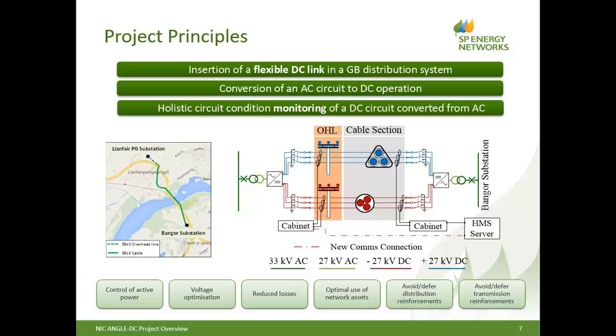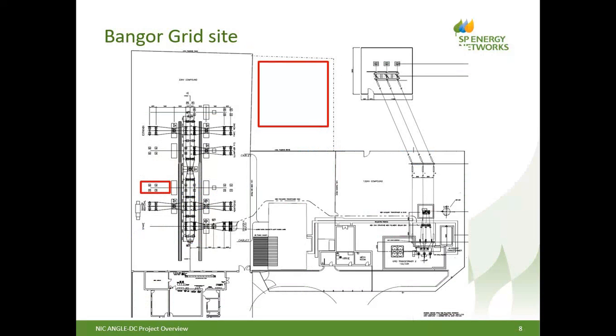The next slide is a quick slide I'll just run through, and that's the Bangor grid site. You can see it's a fairly typical grid site with the 132 on the right hand side and the 33 outdoor compound on the left. So you can see the red boxes: the big box in the middle top of the screen is showing where the MVDC converter station is going to go, and the left hand small red box is the spare bay, where we're going to introduce the new cable circuit connection.